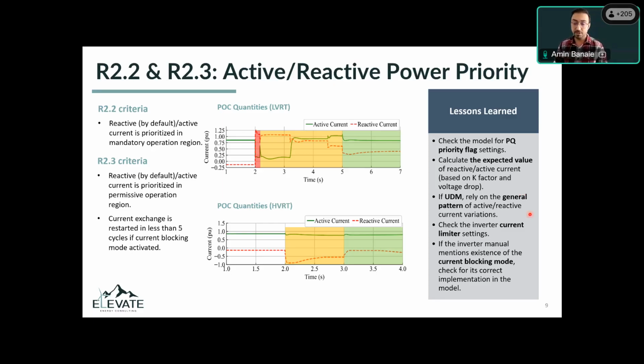If we don't have any of this information, the only way that we can verify this is by just looking at the general pattern of active and reactive current. If you see that active current decreases and reactive current increases for LVRT case, and this general pattern keeps continuing, then that's reactive current priority mode. And for HVRT, active current remains the same, but reactive current drops. That's again an indication of reactive current priority mode.